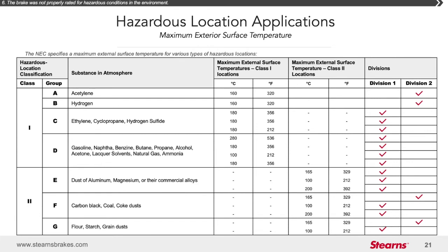The groups are defined as the explosive characteristics of the air mixtures of gases, vapors, or dusts. Materials have been placed in groups based on their ignition temperatures and explosive properties. Class 1 gases and vapors are listed in 4 groups, A, B, C, and D, based on specific properties such as maximum explosive pressure and ignition temperature. Class 2 airborne dusts are listed in 3 groups, E, F, and G. The dust properties considered include thermal and electrical conductivity. The table in this slide provides examples of which materials and external surface temperatures actually make up specific groups.